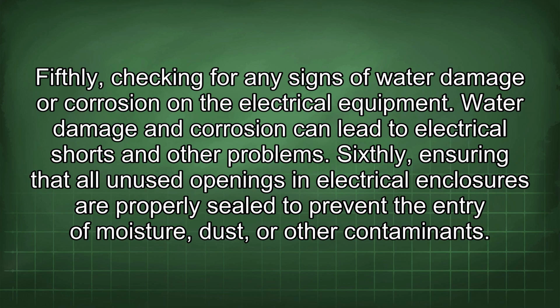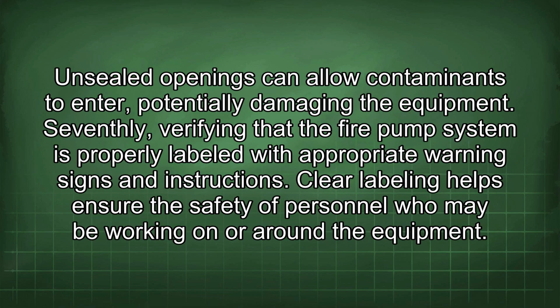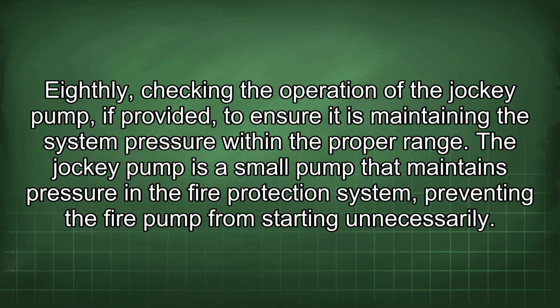Sixthly, ensuring that all unused openings in electrical enclosures are properly sealed to prevent the entry of moisture, dust, or other contaminants. Unsealed openings can allow contaminants to enter, potentially damaging the equipment. Seventhly, verifying that the fire pump system is properly labeled with appropriate warning signs and instructions. Clear labeling helps ensure the safety of personnel who may be working on or around the equipment. Eighthly, checking the operation of the jockey pump, if provided, to ensure it is maintaining the system pressure within the proper range. The jockey pump is a small pump that maintains pressure in the fire protection system, preventing the fire pump from starting unnecessarily.